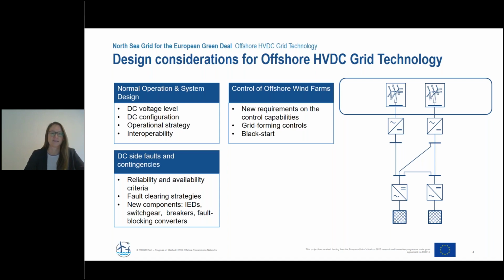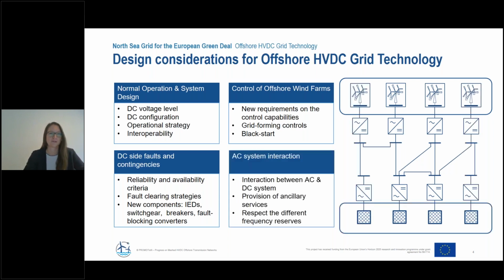The key element here is the new grid forming controls for offshore wind farms that also facilitate new functionalities such as black start. And of course, with systems becoming larger and larger, we also have to take into account the interaction between the AC and DC systems, as they are closely interlinked.